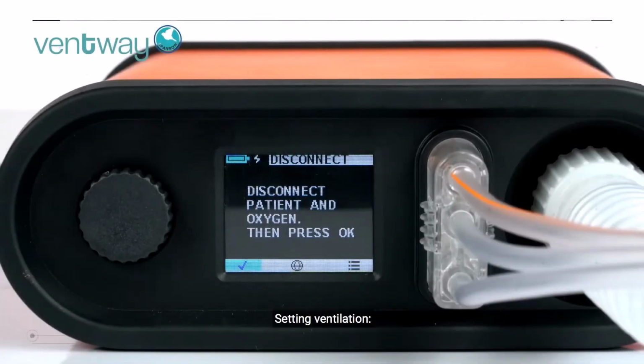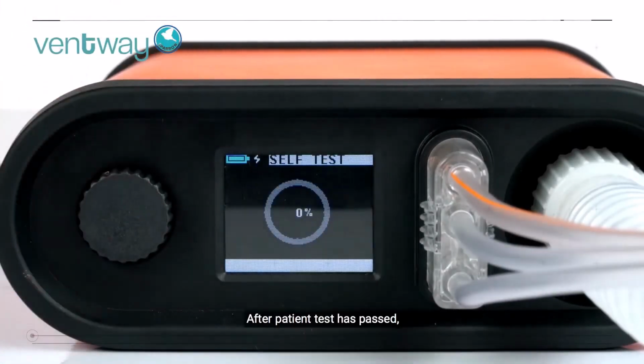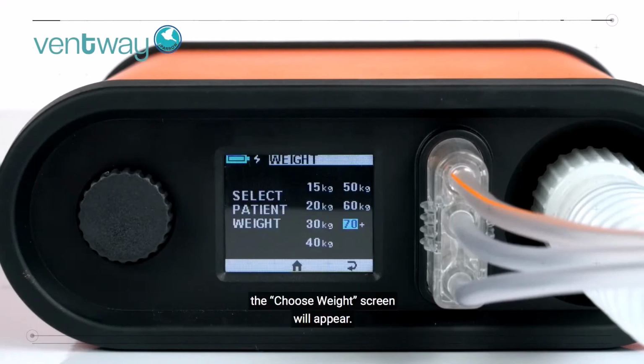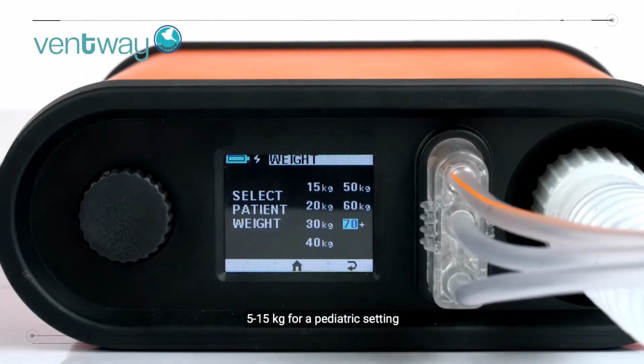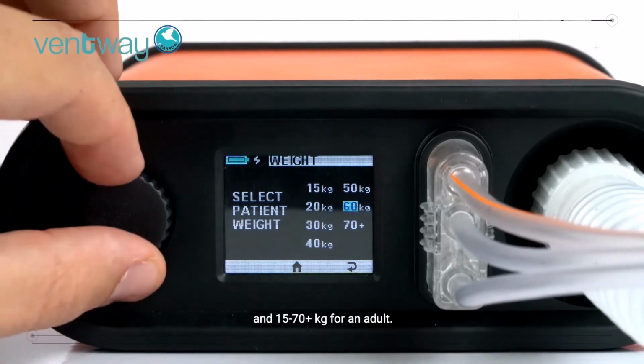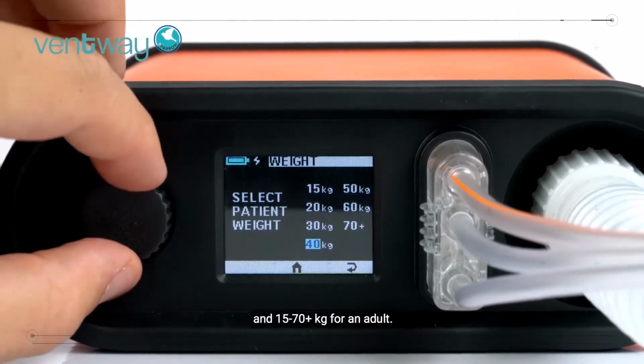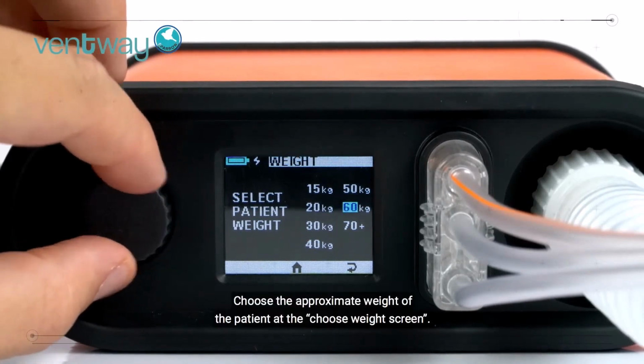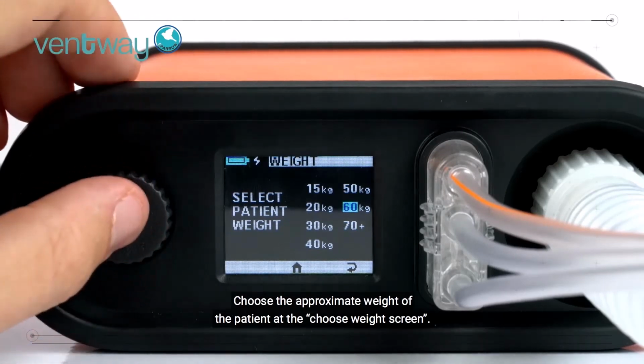Setting ventilation. After the patient test has passed, the Choose Weight screen will appear. The device will recognize whether an adult or a pediatric patient circuit is connected and will set the weight range accordingly: 5 to 15 kilograms for a pediatric setting, and 15 to 70 plus kilograms for an adult. Choose the approximate weight of the patient at the Choose Weight screen.